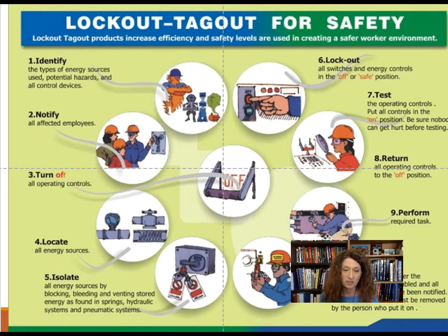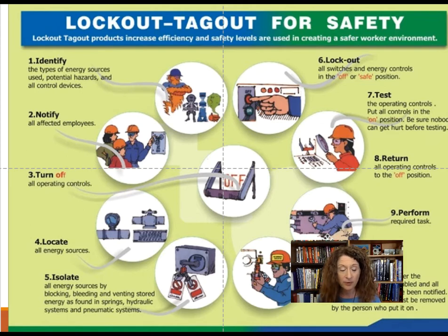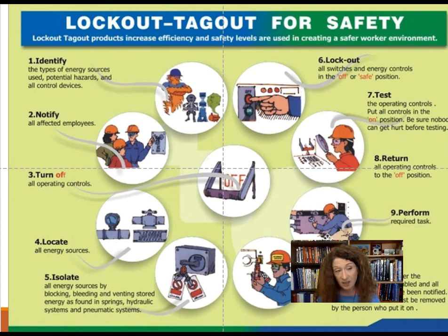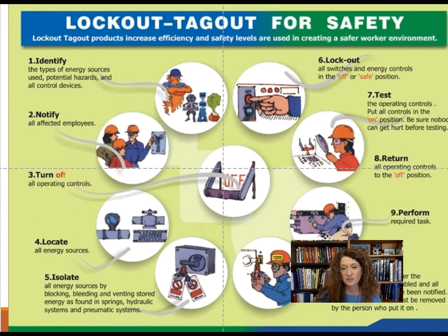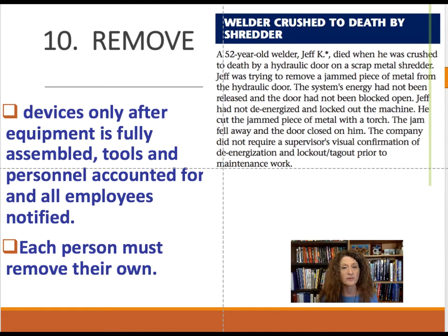Step 9: Perform the task. Step 10: Reassemble in reverse order — make sure all equipment is back together, all tools are removed from the space. At Coal Strip, they count every tool that goes into a confined space, then check them all off a list to make sure nothing is left inside accidentally, because left-behind tools can cause equipment to malfunction. Once everything is verified safe, each person removes their own lock and then you are able to re-energize the source.